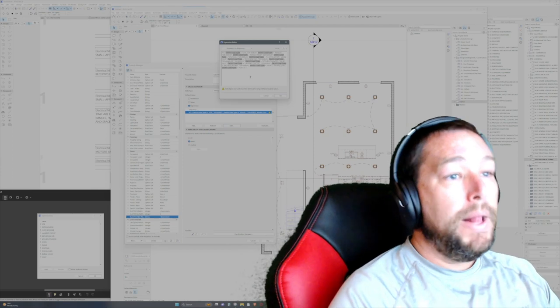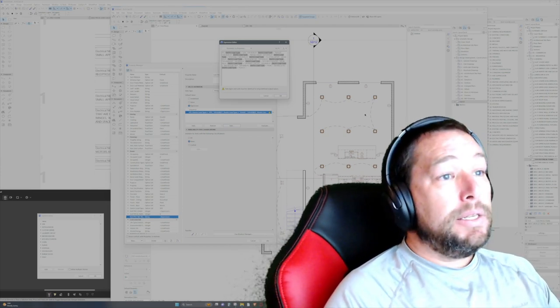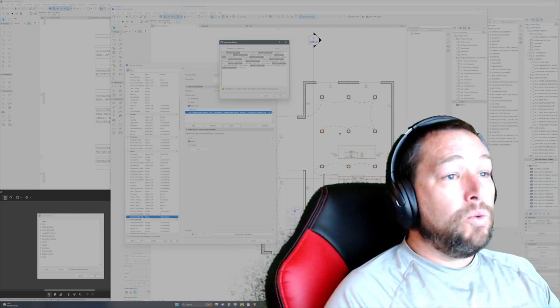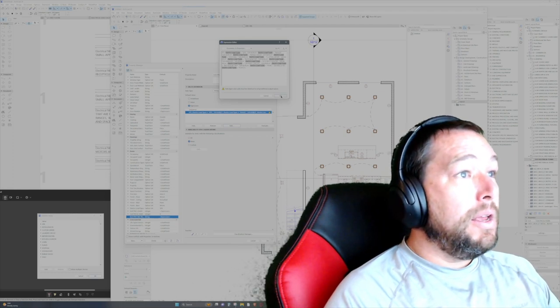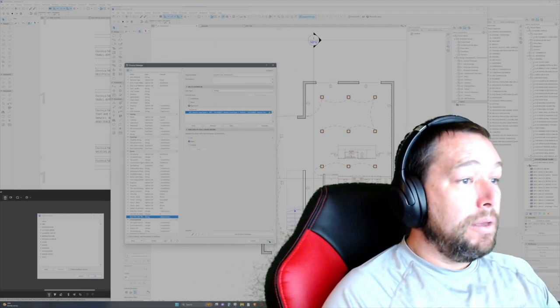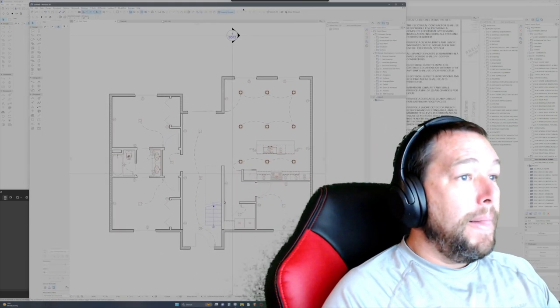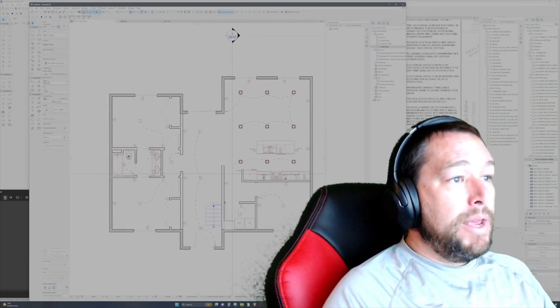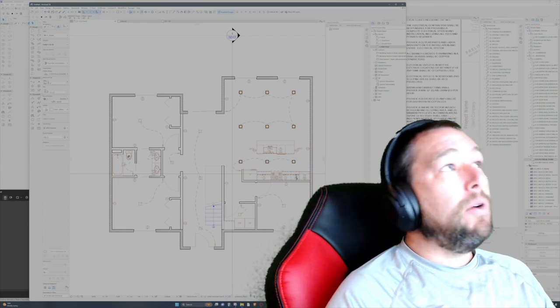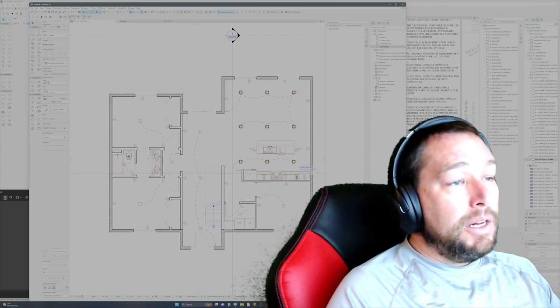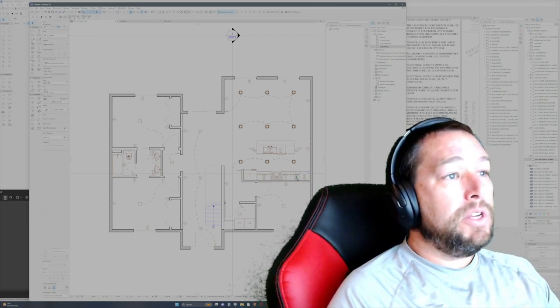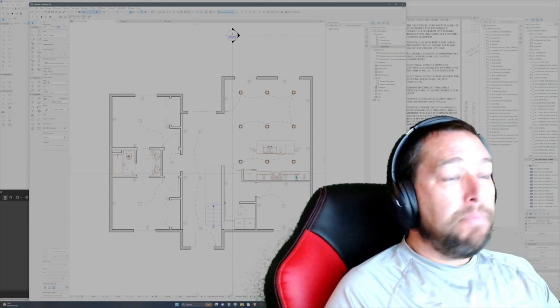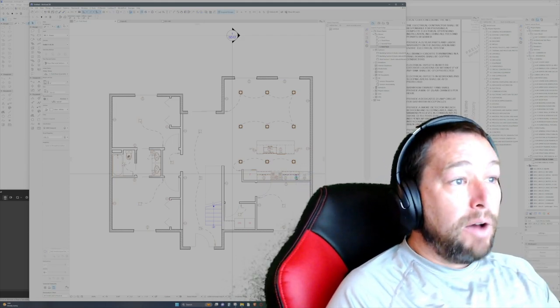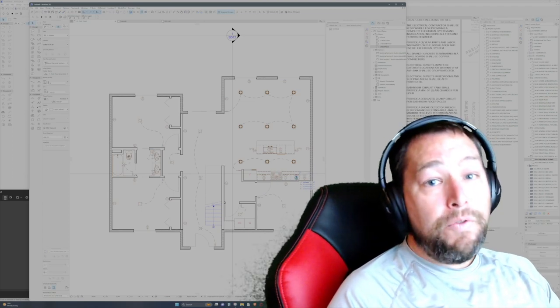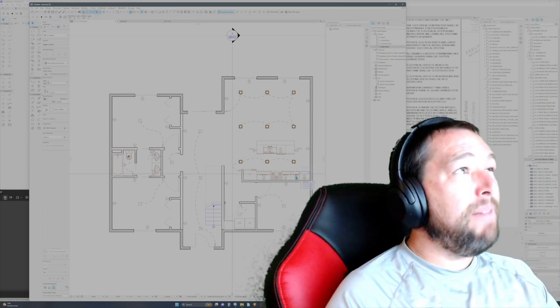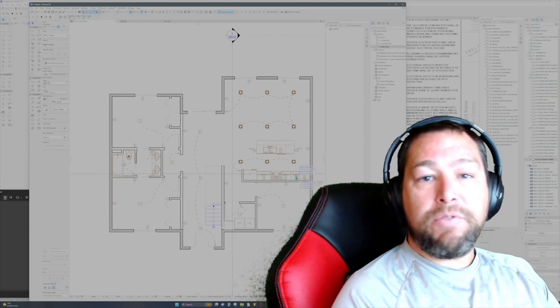For example, if we look at the actual kitchen in which we are designing, you'll notice that we have three outlets on the counter. Now, the code here in the United States requires that small appliance outlets on kitchen counters be no more than 2 feet from any point, so roughly that means about every 4 feet you'll have an outlet.